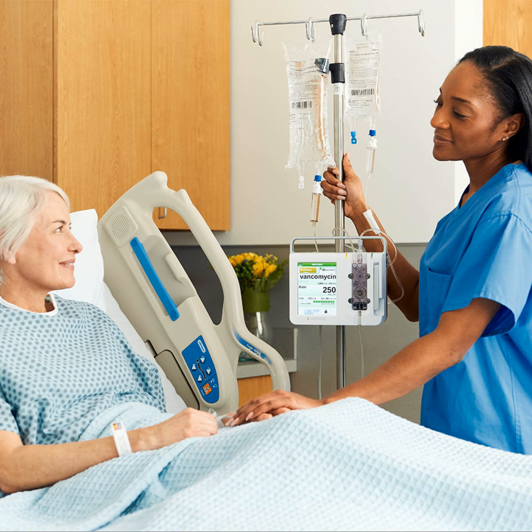As a matter of fact, the pump, with these linear peristaltic ones, requires you to set up the pump at the height of the patient's vascular access site, or the heart. And less than 15% of nurses know that you have to set the pump up at the level of the heart. Also, the pump's IV bag height relative to the IV pump. So where's the first primary bag? And then the height difference between the primary and the secondary IV bags. Now, less than 5% of nurses know why you're hanging bags of your primary and your secondary differently, and using those bag hooks. So if the height difference between the primary and the secondary is not enough, the secondary, or that piggyback, may not infuse.